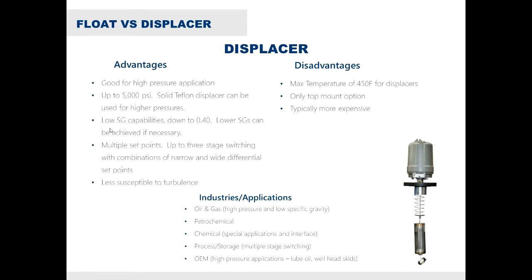Displacers are also less susceptible to turbulence. The biggest disadvantage with displacers is going to be temperature. Anything above 450 degrees requires using a float, because the spring used on a displacer-based level switch is not good for temperatures above 450 degrees — springs actually lose their spring force at higher temperatures. Essentially, if that spring force is lost, you lose the capabilities of the level switch. The other disadvantage is the only top mount option, and displacer-type level switches are typically more expensive than float-based switches.